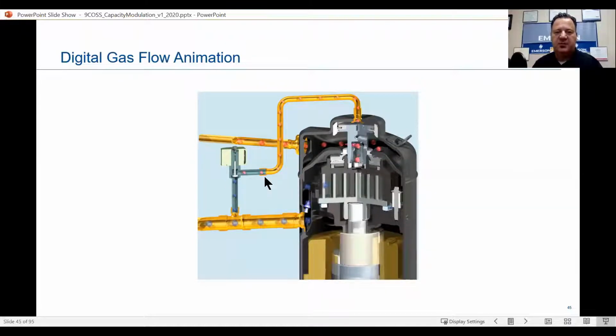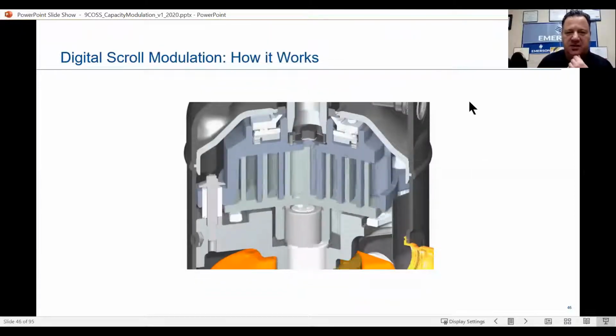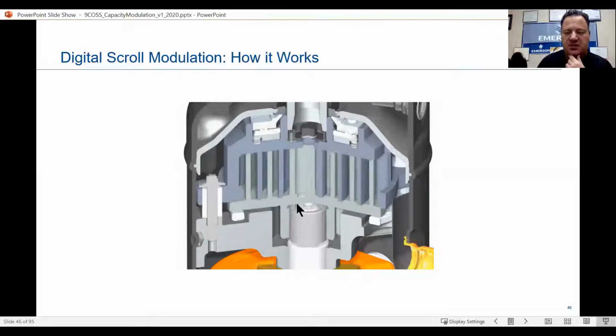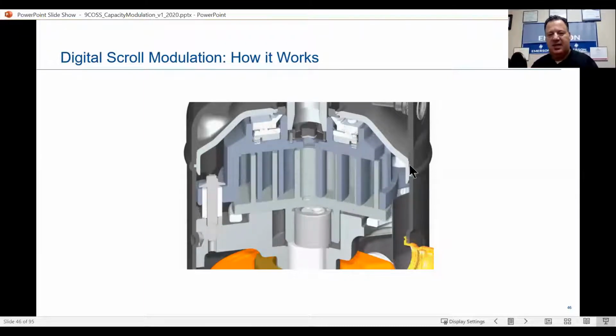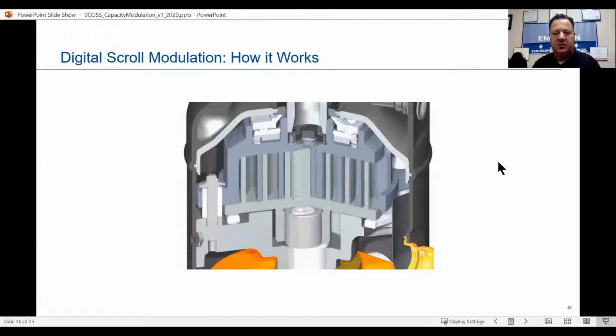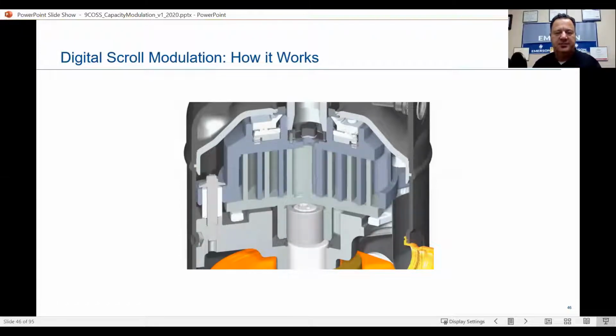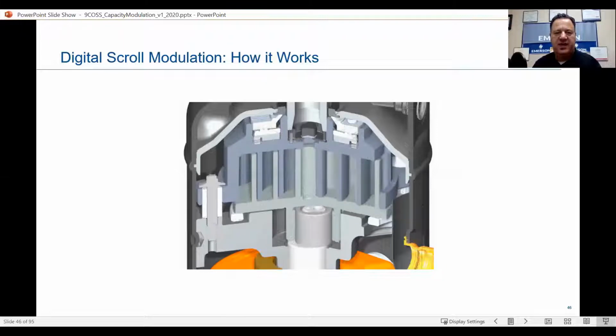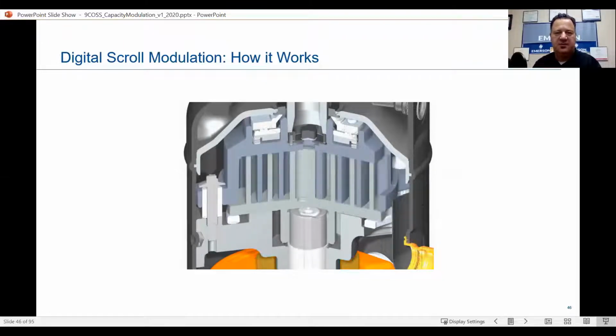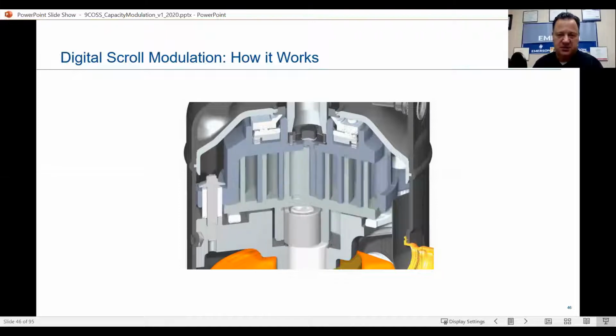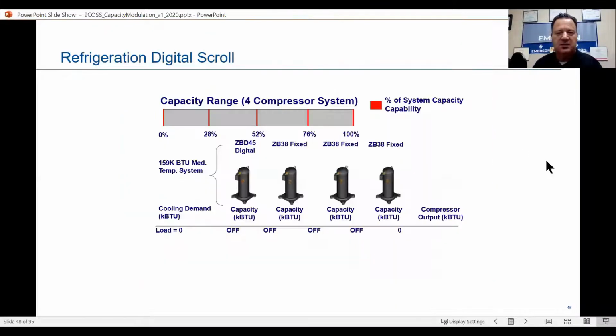Now, if you were to detect some type of problem here, there's a lot of different ways you can attack this. You can pinch off this tube if you like. If this fails, it's going to be like a fixed compressor, basically. And this is just a larger picture of a digital scroll modulation and how it works. You can see the same concept. The speed of it's slightly exaggerated here. Again, the scrolls run 3,500 RPMs. If you didn't know that, they're 2-pole motors. All right, so they're running twice as fast as the 4-pole motors, which would be like 1,750 RPMs at 60 hertz. So Copeland Scroll Digital, let's take a look at this in some applications.